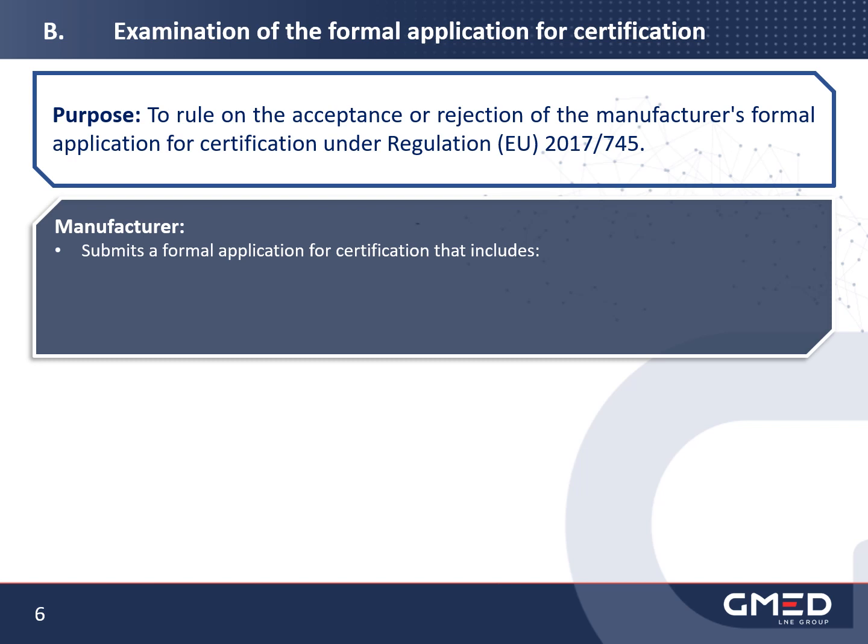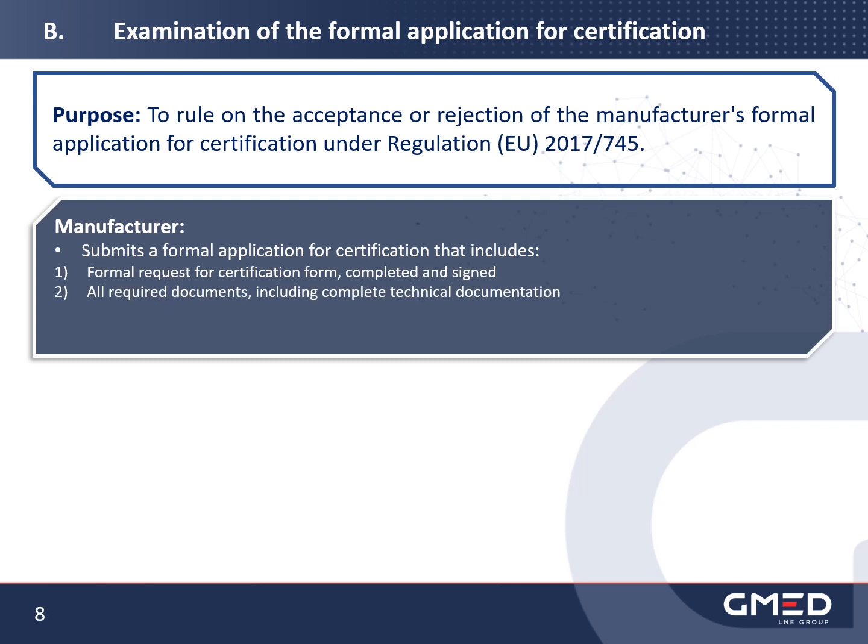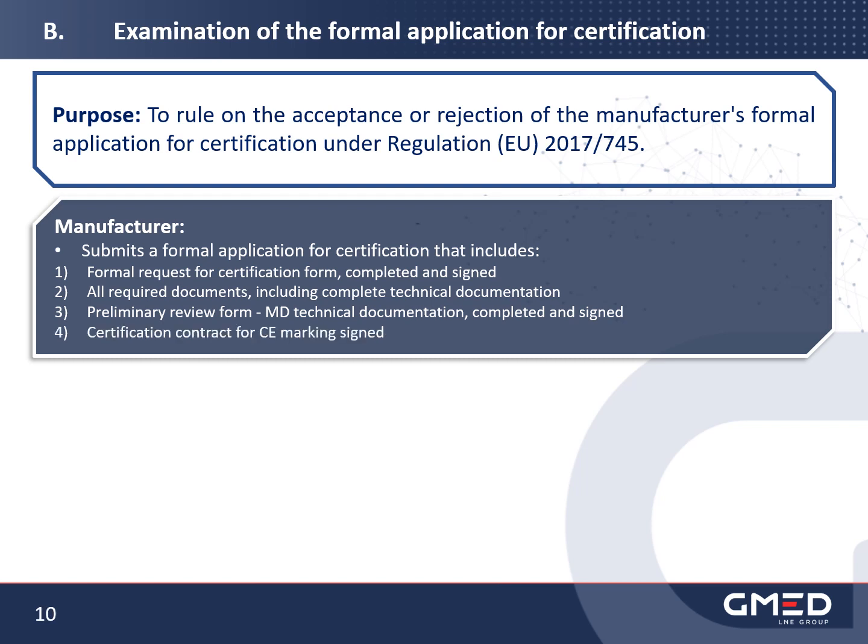To achieve this goal, the manufacturer must submit a formal application for certification, which includes a formal request for certification form, completed and signed, all of the documents requested and expected by GMED, including the complete technical documentation for each device for which the technical documentation assessment service is to be carried out, with a view of issuing a certificate, a preliminary review medical device technical documentation form, completed and signed for each technical documentation submitted, and the certification contract for CE marking under Regulation EU 2017/745 signed.